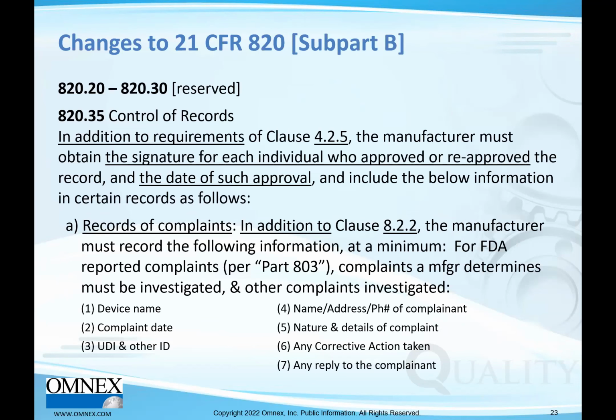820 paragraphs 20 through 30 are reserved. Right now they're being used, but they are covered by 13485, so those paragraphs are now blank, reserved for future use. Paragraph 35, control of records. In addition to the requirements of clause 4.2.5, the signature for each individual who approved or reapproved a record and the date of such approval must be in place in the records.